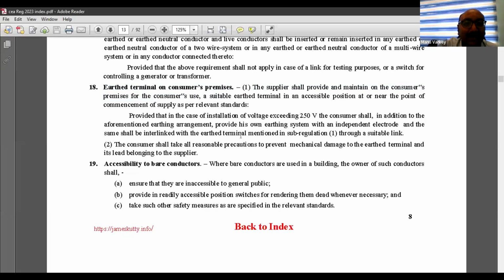Yes, sir. Regulation 18 makes it mandatory for the supplier to provide an earth terminal at the consumer premises. If it is a single phase consumer, the consumer is under no obligation to provide an additional earth terminal. But in the case of a three phase consumer, he has to provide an additional earth terminal, which he has to link with the earth terminal provided by the supplier. So an earth terminal in this regard means a multiple earth neutral terminal, an earth derived from a multiple earth neutral terminal, if you read this in line with the other CEA regulations. Thank you, Manoj ji.